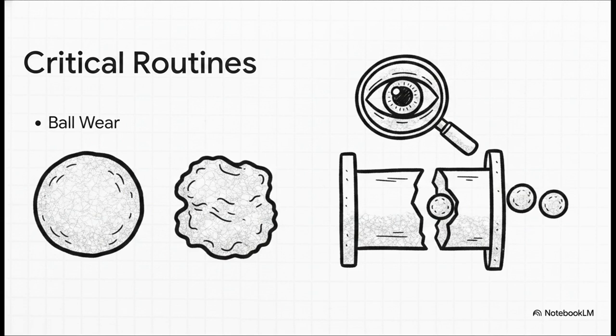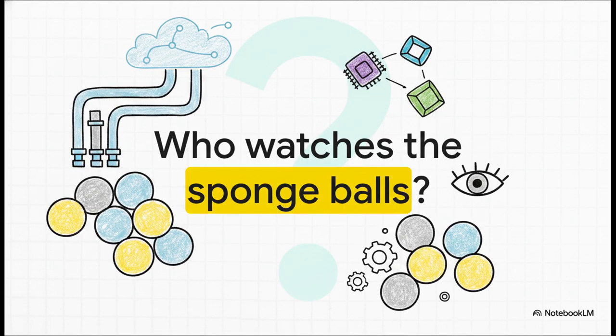Number two, track ball loss. If that hydrodynamic strainer acts up, balls can escape the loop and get flushed right out into the external cooling tower. So checking daily recovery counts on the control panel is essential. If you shoot 100 balls in and only 90 come back, well, you've got a problem you need to look into immediately. Which leaves us with a fascinating final thought to wrap up this explainer.